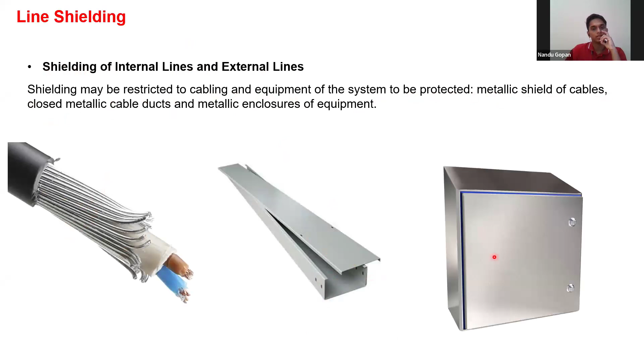Next is line shielding - shielding of internal or external lines. If there is any line coming outside or inside, you are supposed to shield it. Shielding shall be restricted to cables and equipment of the system to be protected, using the metallic shield of the cable, closed metal cable ducts, or metallic enclosures of the equipment. So you bond the armoring, or the metallic cable tray, and if there's equipment inside an enclosure, you bond that enclosure too.